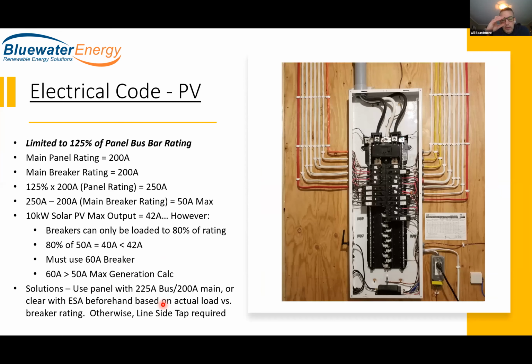Okay, electrical code with regards to connecting photovoltaics. Essentially the PV system becomes a generator, as I mentioned earlier, and a 10 kilowatt array, with a 10 kilowatt inverter, is essentially 42 amps of current at 240 volts. There is a limitation in code with regards to how much generation we can backfeed onto a load center. Here's a panel, everybody's seen them. One of these goes in every home, circuit breakers go on the panel, and these feed the loads in the home. So this is a load center.